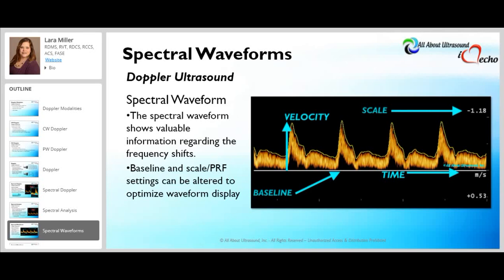However, keep in mind that there is an invert control that's available, and sometimes this might be utilized to display arterial waveforms above the baseline and venous waveforms below the baseline. That does not necessarily mean that it is a positive or negative frequency shift, so you have to make sure that all factors are considered with regard to the display and whether or not the invert option or control has been applied.